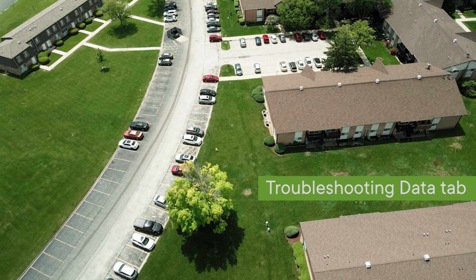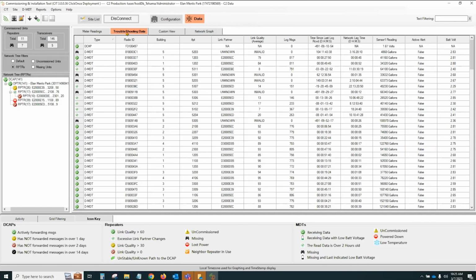Troubleshooting Data tab. Now let's look at Network Health and Troubleshooting, located under the Troubleshooting Data tab. The columns here show data such as the link quality, battery voltage, and the most recent link partner. The link partner is the device an MDT or repeater is directly communicating with.